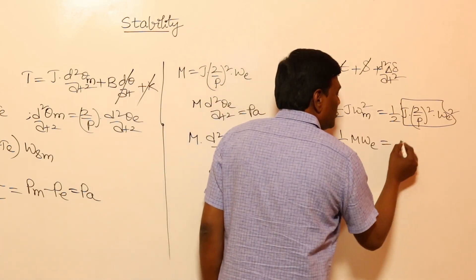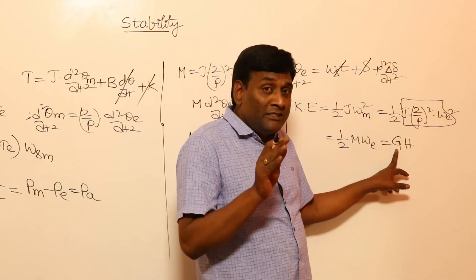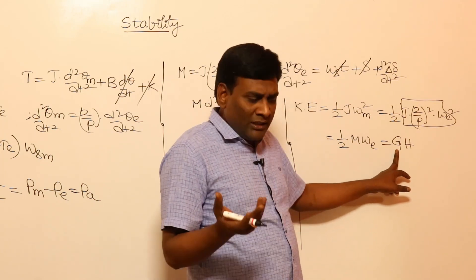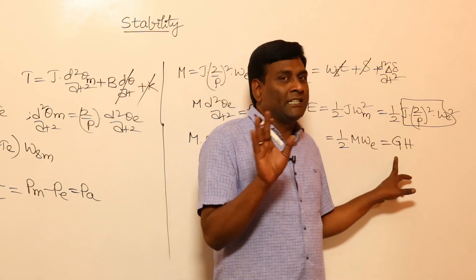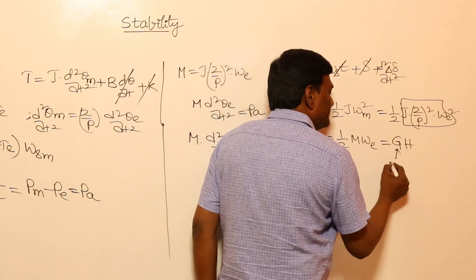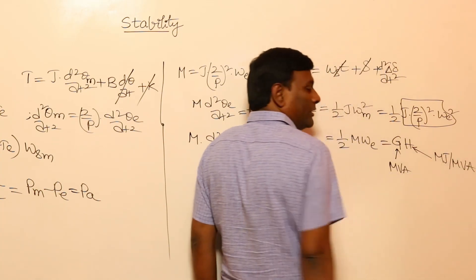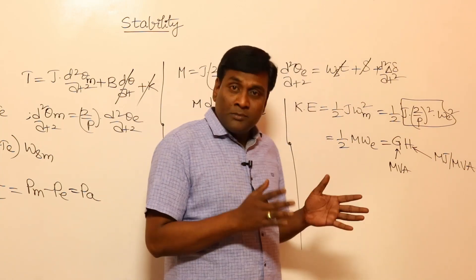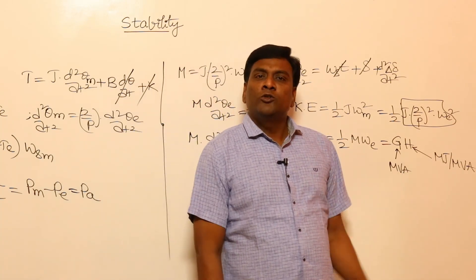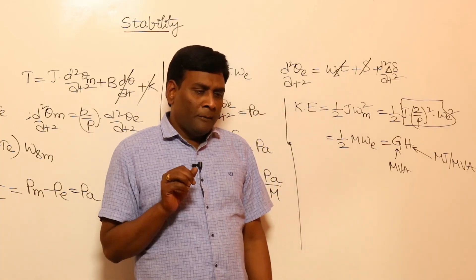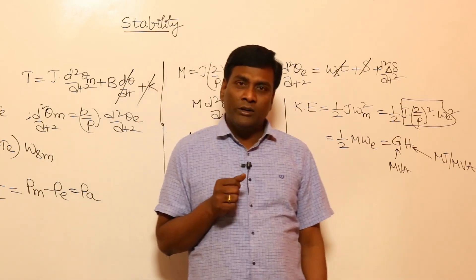G is the machine rating in MVA, and H has units of mega joules per MVA. Many textbooks use G instead of S for MVA rating — it is just a terminology difference. H is given in mega joules per MVA, and for any given synchronous machine, the datasheet typically provides H — for example, 3 mega joules per MVA — telling us how much kinetic energy is stored per MVA of capacity.